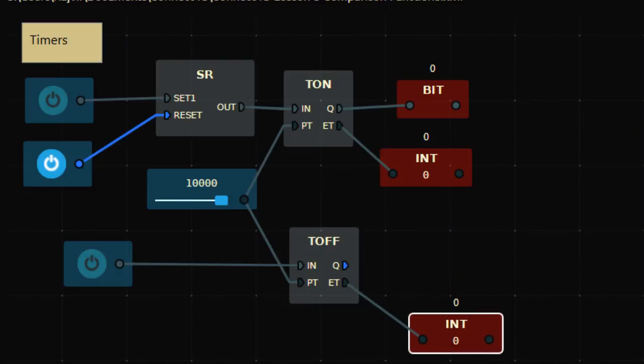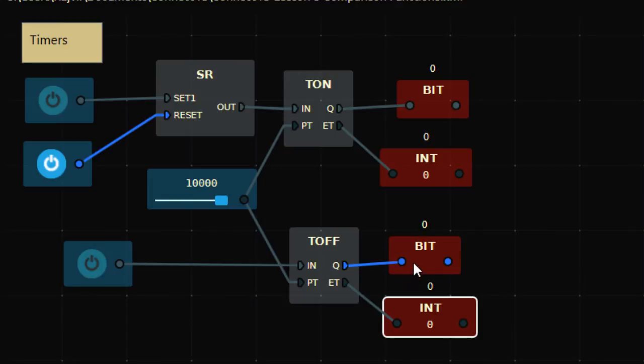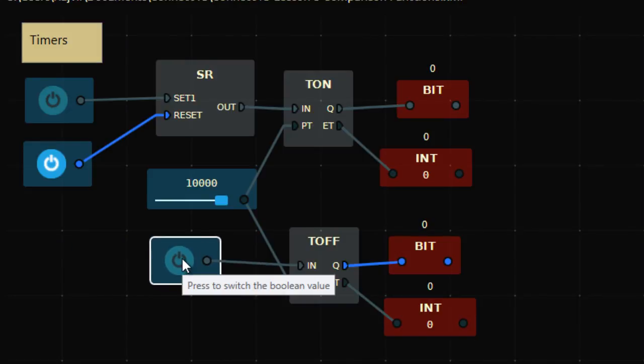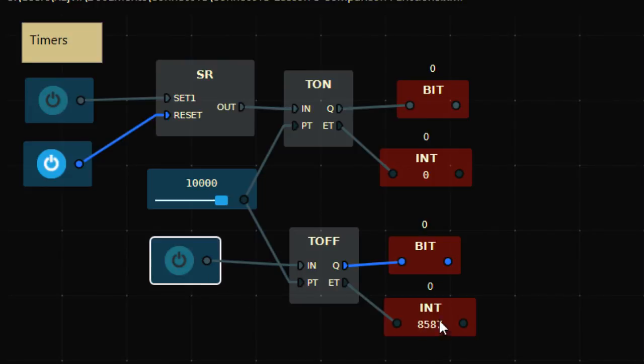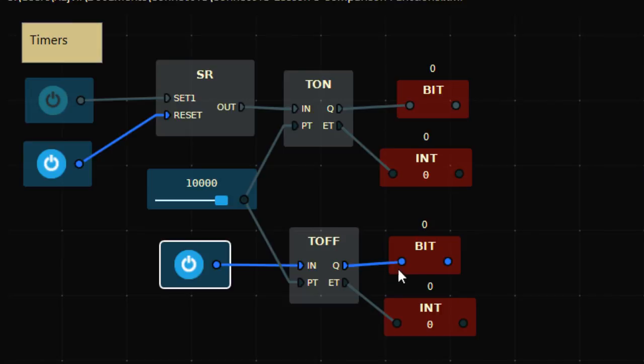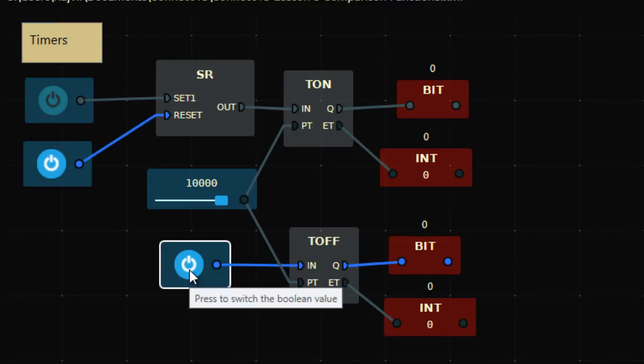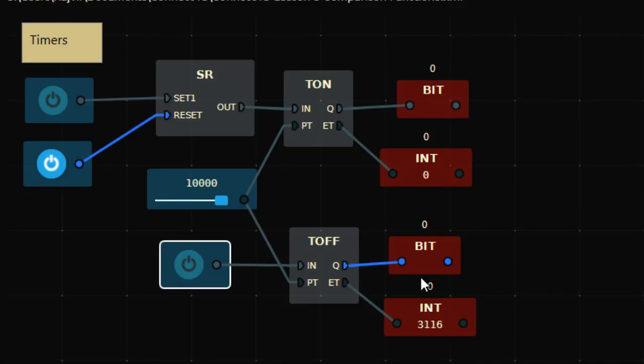Right now the output bit is ON. This timer says the output will be ON for another 10 seconds — the delay set at PT. If I press the switch it doesn't change anything, but when I turn the input OFF, the output will remain ON and then turn OFF after 10 seconds. The timer starts counting from the true-to-false transition at the input.